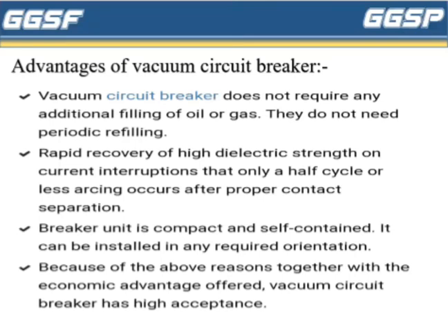Advantages of vacuum circuit breaker. Vacuum circuit breaker does not require any additional filling of oil or gas. They do not need periodic refilling. Rapid recovery of high dielectric strength on current interruption. Only a half cycle or less of arcing occurs after proper contact separation. The breaker unit is compact and self-contained. It can be installed in any required orientation. Because of the above reasons, together with the economic advantage offered, the vacuum circuit breaker has high acceptance.